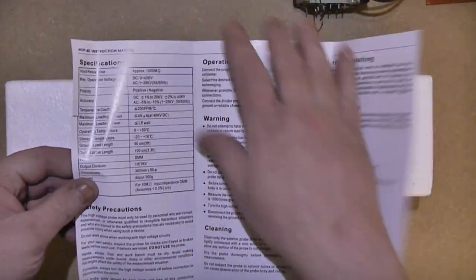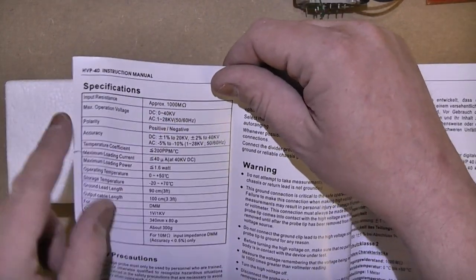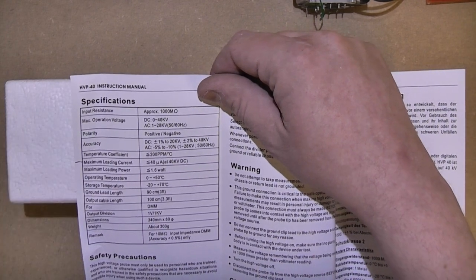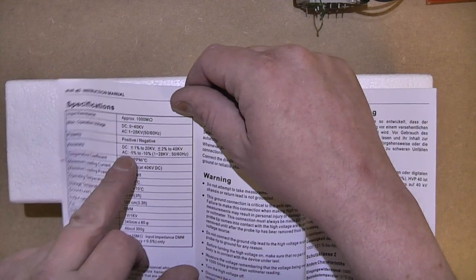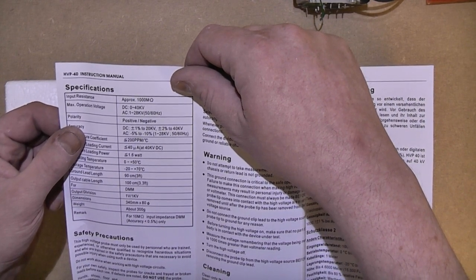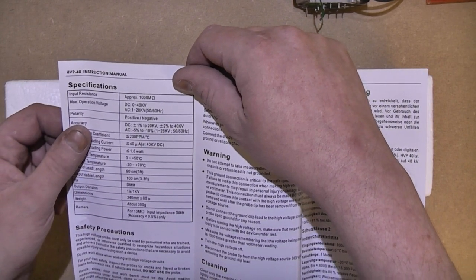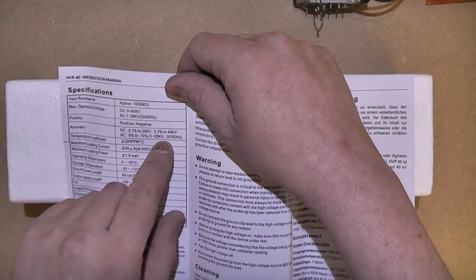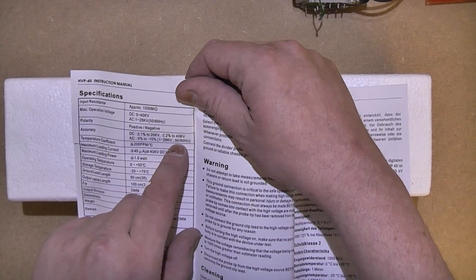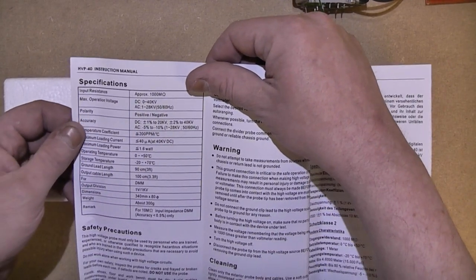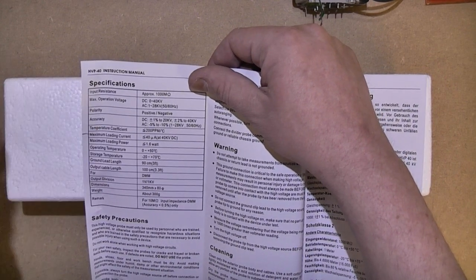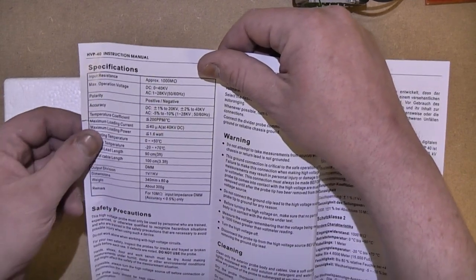Here's English, here's the specifications. Really I mean it's a thousand mega ohms, so basically it's a resistive divider. It uses, most multimeters their input impedance is 10 mega ohms. I've measured mine, it is 10 mega ohm. There's accuracy, you know 1% up to 20 kV, 2% plus or minus to 40 kV. AC is a bit minus 5% minus 10, 1 to 28 kV. The important thing, they've actually stated it's for normal line frequency operation, therefore 50 60 hertz. So if you had a high frequency flyback transformer, ones without the built-in blocking diode like for driving neon tubes and stuff like that, because the frequency is so high the self-capacitance between the resistors would have caused overheating. That's why they've stated 50 or 60 hertz.